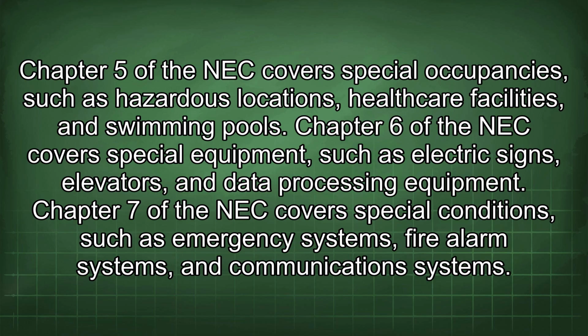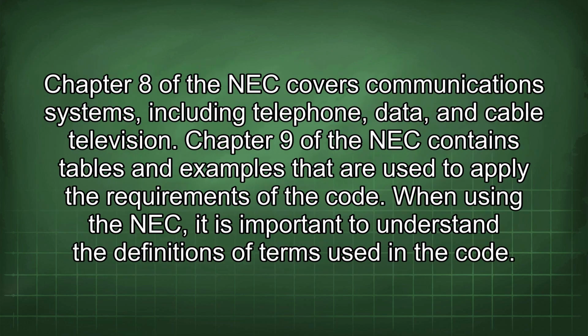Chapter 5 of the NEC covers special occupancies, such as hazardous locations, healthcare facilities, and swimming pools. Chapter 6 covers special equipment, such as electric signs, elevators, and data processing equipment. Chapter 7 covers special conditions, such as emergency systems, fire alarm systems, and communications systems. Chapter 8 covers communications systems, including telephone, data, and cable television. Chapter 9 contains tables and examples used to apply the requirements of the code.